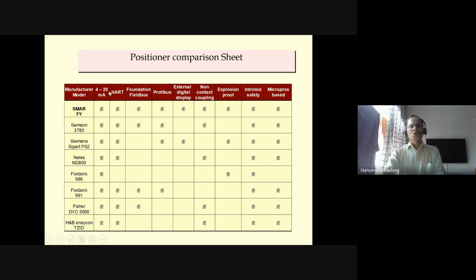So first you have to see that 4 to 20 mA signal, HART signal means pure analog signal, HART signal, Foundation Fieldbus, Profibus, external digital display, non-contact coupling, X-proof, intrinsic safety, and microprocessor base. These are the standard, or we can say important, specifications for the smart valve positioners. So you have to define whether your valve is giving 4 to 20 milliampere HART or Foundation like this.